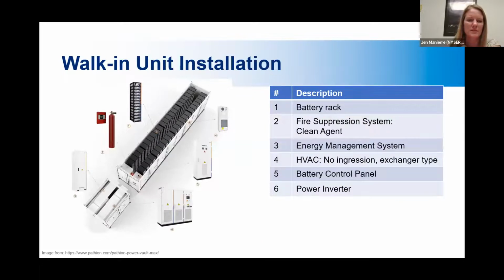This is a bird's eye cutaway view of what it might look like on the inside of one of these. You can see all of the battery racks, which are the black boxes taking up the vast majority of the space, but you're also going to see the fire suppression system. Could be a clean agent, like I said before, could be water, could be a combination of both. The energy management system might be in there, or located just outside the box if it's shared with some of the other containers.